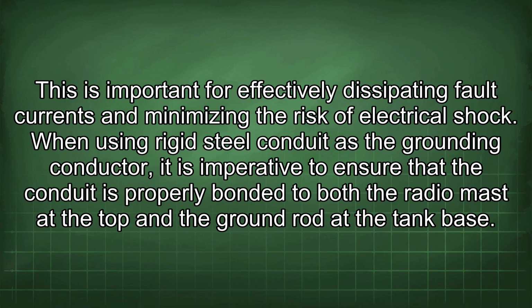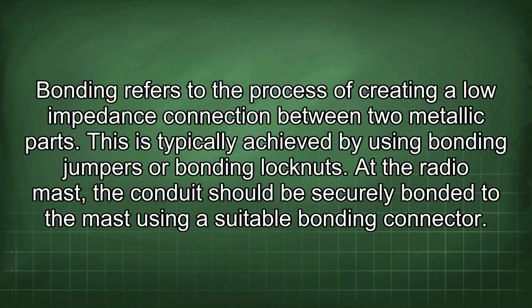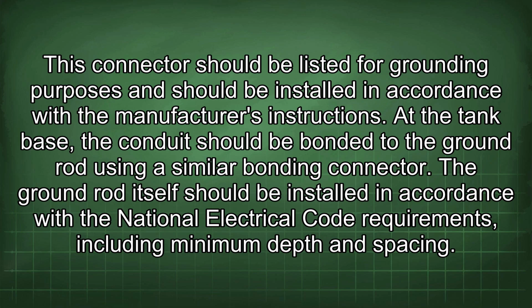When using rigid steel conduit as the grounding conductor, it is imperative to ensure that the conduit is properly bonded to both the radio mast at the top and the ground rod at the tank base. Bonding refers to the process of creating a low impedance connection between two metallic parts. This is typically achieved by using bonding jumpers or bonding locknuts. At the radio mast, the conduit should be securely bonded to the mast using a suitable bonding connector. This connector should be listed for grounding purposes and should be installed in accordance with the manufacturer's instructions. At the tank base, the conduit should be bonded to the ground rod using a similar bonding connector. The ground rod itself should be installed in accordance with the National Electrical Code requirements, including minimum depth and spacing.